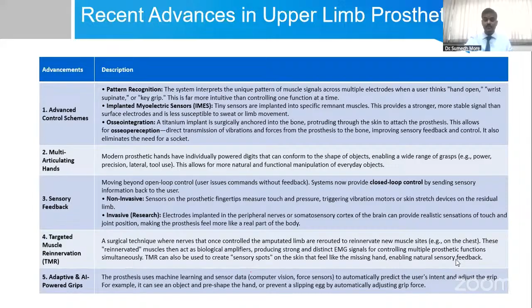So here in the advanced control system there is pattern recognition. The system interprets the unique pattern of the muscle signal across multiple electrodes. When a user thinks hand open, the wrist supinates or key grips. This is far more intuitive than controlling one function at a time. The other part is the implanted myoelectric sensor, that is IMES. The tiny sensors are implanted into specific remnant muscles. This provides a stronger, more stable signal than surface electrodes and is less susceptible to sweat or limb movement.